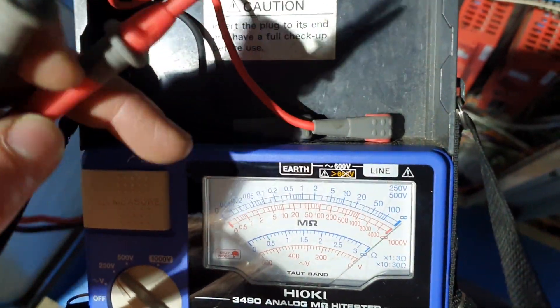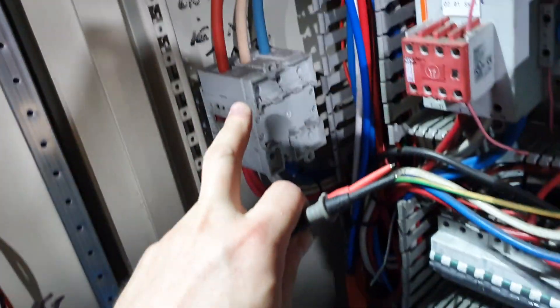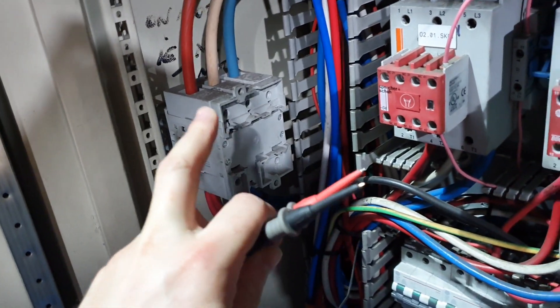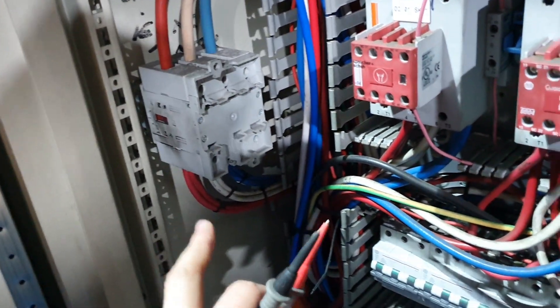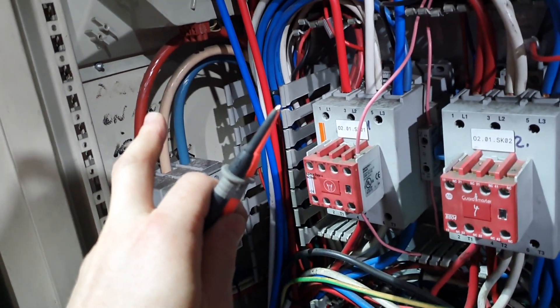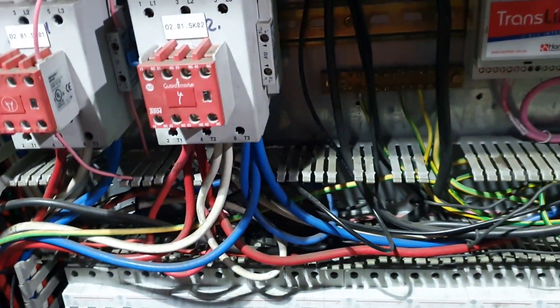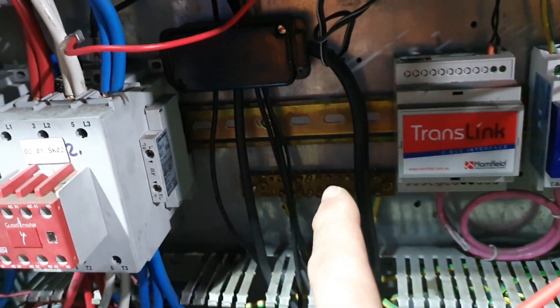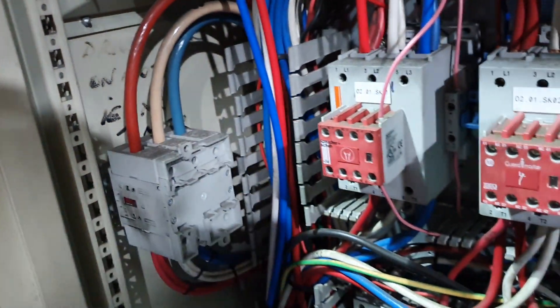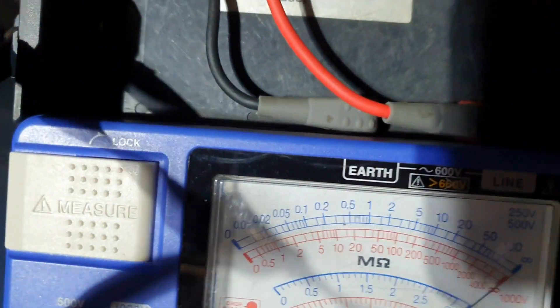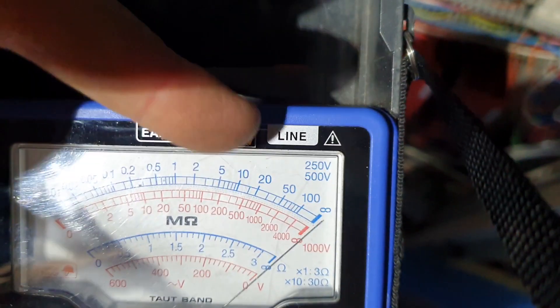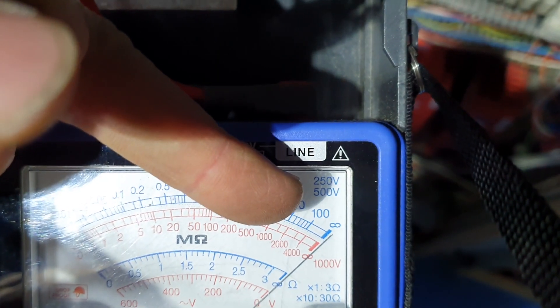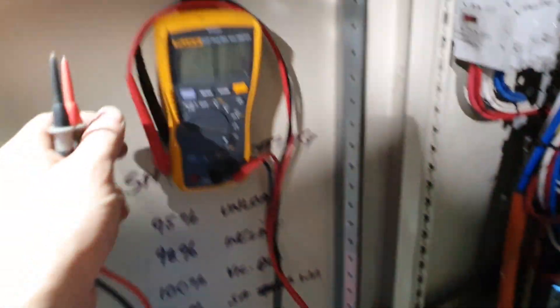So you'll have to take my word for it, but I just megaed the line-sided isolator here. Turned the isolator off so the panel's isolated. I just want to know that this cable's okay. Because these fuses tripping is a big deal. So I've tested Earth, Neutral, and ABC. And everything is pretty well on infinite scale, which is pretty good. Flips down to about 50 megaohms and then just creeps back up. So that's a good result for me.